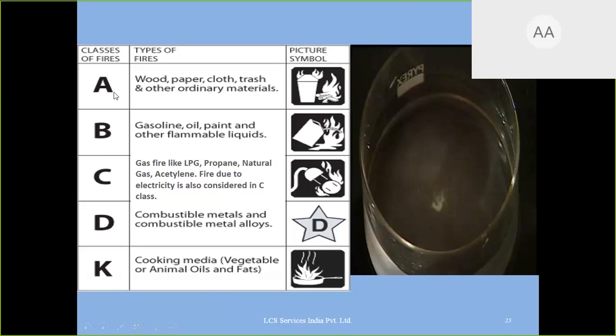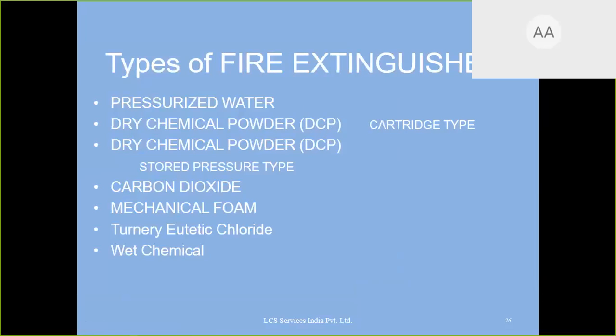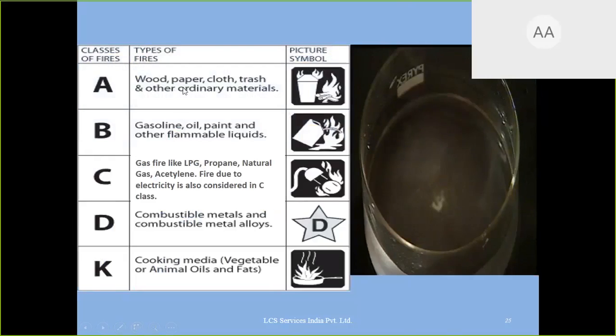So coming back to A, B, C, D and K. A solid, B liquid, C gas. Right? Solid, liquid, gas and electricity. Now which are the fire extinguishers used for this? So if you see fire extinguisher, we have one is pressurized water. There is a fire extinguisher which contains water and it can be used only in the A class fire, not in B and C or D or K. Water can be used only in A class because it is paper, clothes, trash.